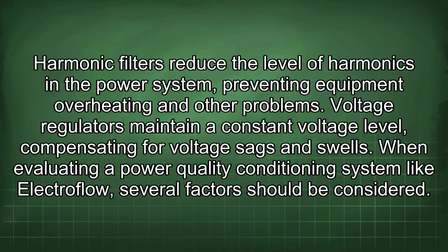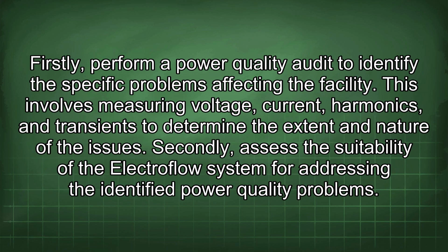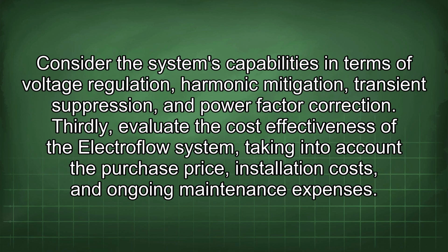When evaluating a power quality conditioning system like Electroflow, several factors should be considered. Firstly, perform a power quality audit to identify the specific problems affecting the facility. This involves measuring voltage, current, harmonics, and transients to determine the extent and nature of the issues. Secondly, assess the suitability of the Electroflow system for addressing the identified power quality problems. Consider the system's capabilities in terms of voltage regulation, harmonic mitigation, transient suppression, and power factor correction.